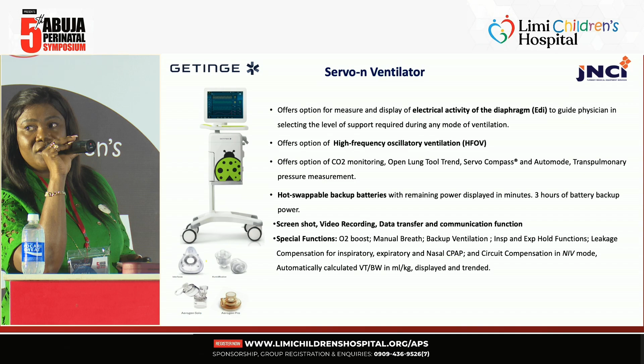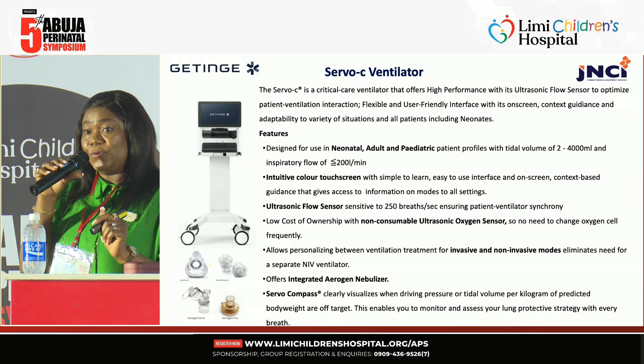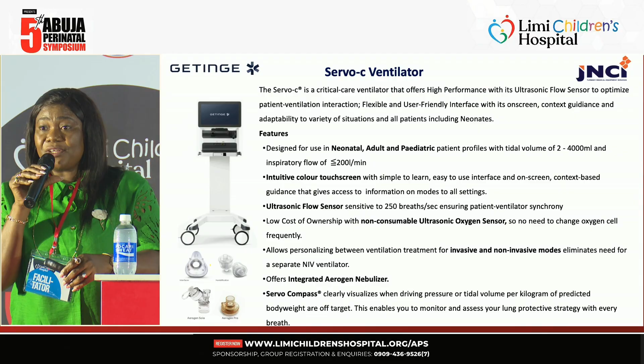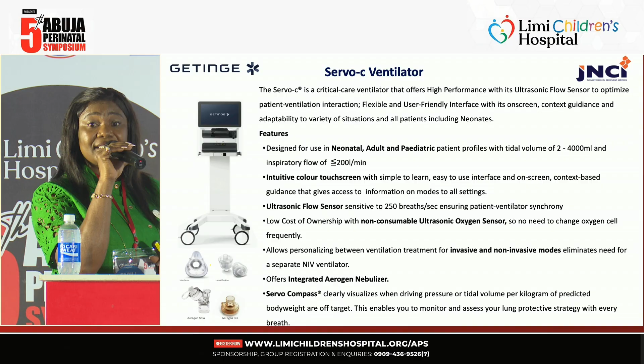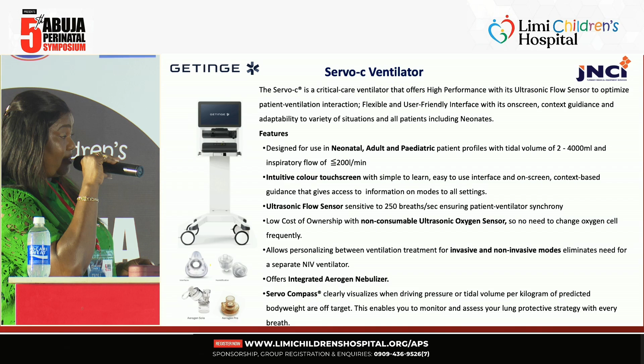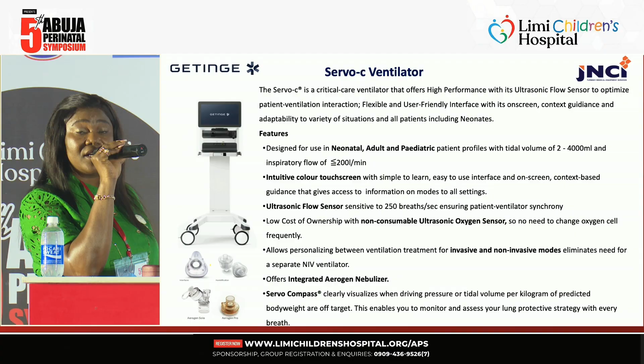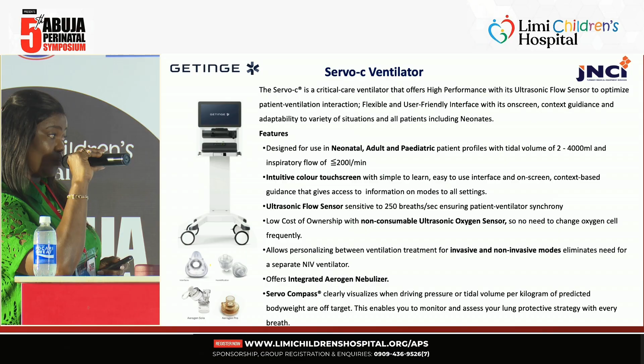Now, another brand of our servo ventilator is the Servo C ventilator. I earlier spoke about the Servo N. This is the Servo C. Servo N is strictly designated to neonatal care. However, the Servo C has the capacity to do the neonates, pediatrics, and adult ventilator. So it is a universal ventilator, a 3-in-1 ventilator. It has the capacity of 2 to 4,000 mils of tidal volume delivery. So this is a ventilator that is designed for such use. Still donning the ultrasonic flow sensor. It has a 15-inch colored touch screen. It also has the integrated nebulizer as well.